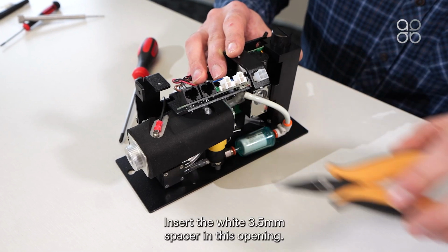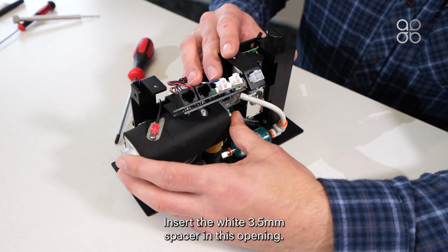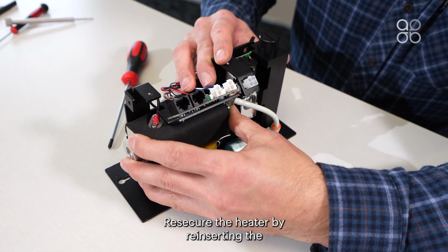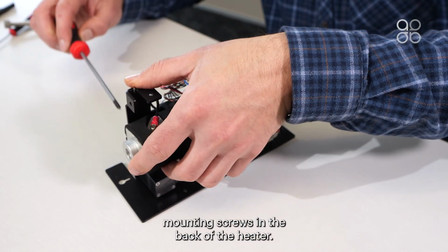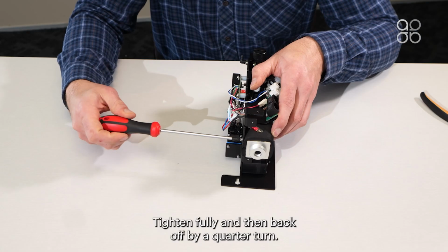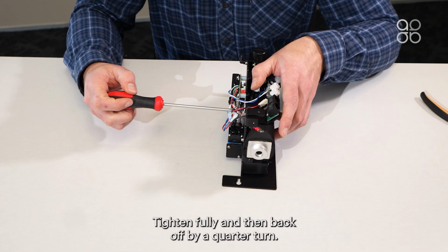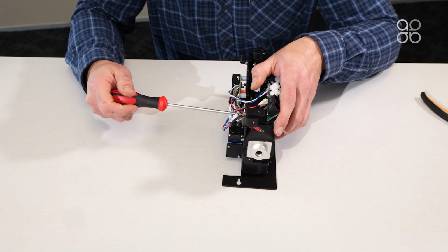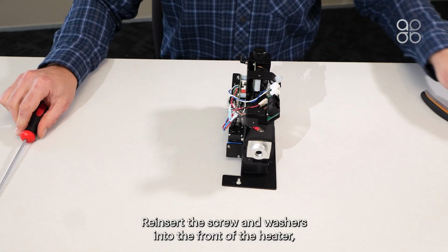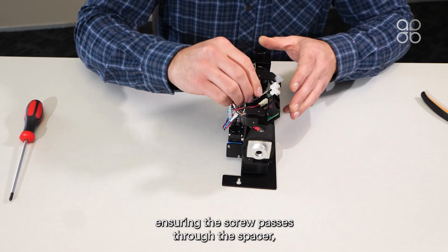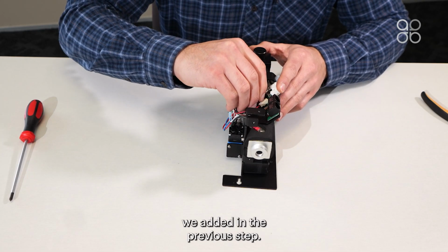Insert the white 3.5mm spacer in this opening. Resecure the heater by reinserting the mounting screws in the back of the heater. Tighten fully and then back off by a 1/4 turn. Reinsert the screw and washers into the front of the heater, ensuring the screw passes through the spacer we added in the previous step.